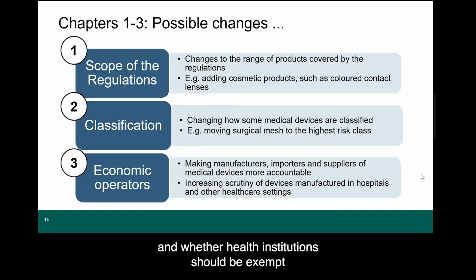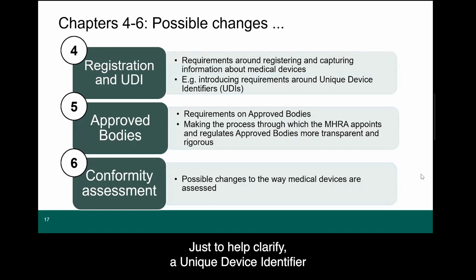Chapter 4 covers the process for registering a device with the MHRA and how devices could be identified with a unique device identifier. And just to help clarify, a unique device identifier is a unique code, often referred to as a UDI, that enables identification of a specific medical device on the market. This code is created through a globally accepted device identification coding standard.